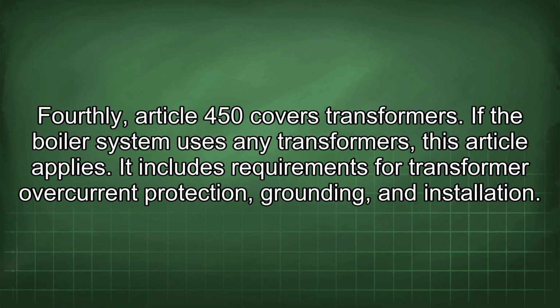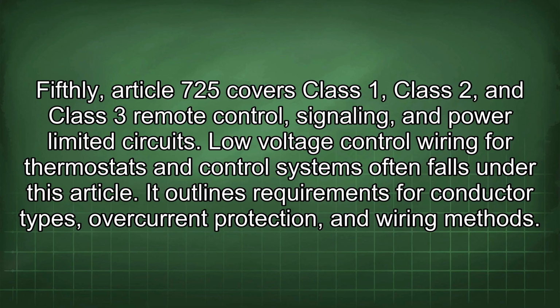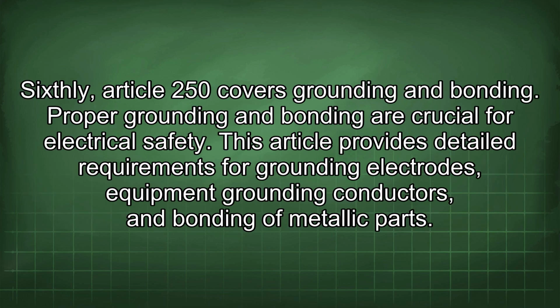Fourthly, Article 450 covers transformers. If the boiler system uses any transformers, this article applies. It includes requirements for transformer overcurrent protection, grounding, and installation. Fifthly, Article 725 covers Class 1, Class 2, and Class 3 remote control, signaling, and power-limited circuits. Low-voltage control wiring for thermostats and control systems often falls under this article. It outlines requirements for conductor types, overcurrent protection, and wiring methods. Sixthly, Article 250 covers grounding and bonding. Proper grounding and bonding are crucial for electrical safety. This article provides detailed requirements for grounding electrodes, equipment grounding conductors, and bonding of metallic parts.